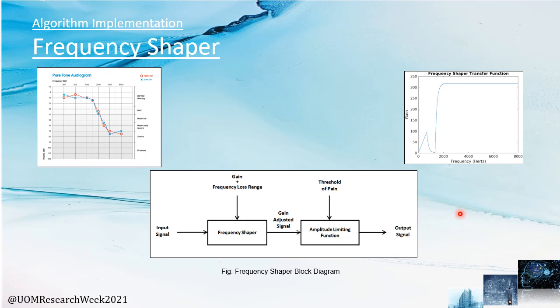The final step of the speech enhancement process is the gain adjustment of the hearing aid. For that, we used a frequency-shaping function. According to each hearing-impaired individual, referring to their audiogram, we can set the hearing loss range and the gain needed to make that range audible to the patient. We also control the maximum output so as not to surpass the pain threshold of the individual. Here you can see an audiogram of a patient with high-frequency hearing loss, and here is the gain-adjusted signal for that patient.